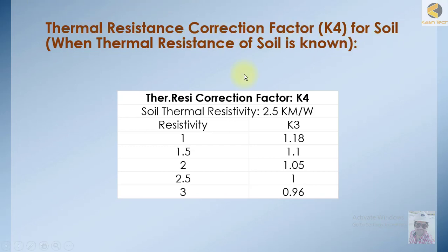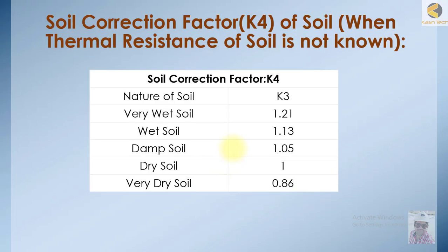Then we have the thermal resistivity correction factor K4 for soil, when the thermal resistivity of soil is known. Thermal resistivity means how much the soil can conduct temperature. If it is good at conducting temperature, its thermal resistivity is good, so the derating factor will be less, and vice versa.